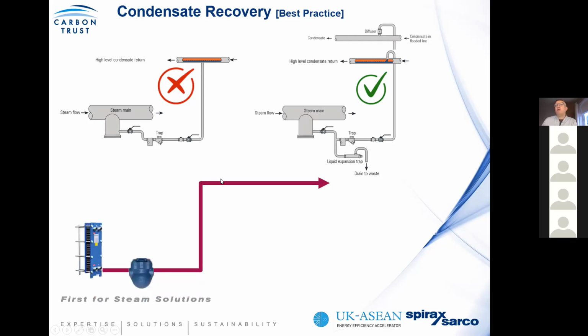Now, what we also need to consider is that for most of your applications, you are basically draining out of a heat exchanger, for example, into a trap, up through an elevated header, like in this scenario here, back into your condensate line. However, what we need to understand is why systems operate and what can cause stall. Stall is the term given when a heat exchanger is struggling to impart heat such that you cannot achieve the temperature set point, or under certain duties, it's failing to perform as it should.